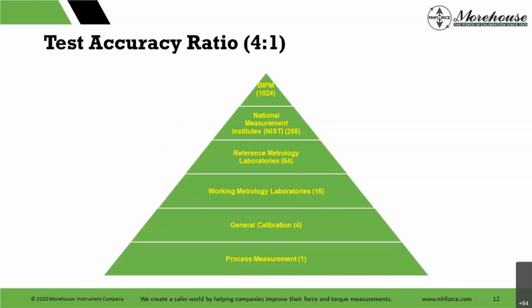Okay, thanks. So talking about accuracy, talking about uncertainties, there's this concept called T.U.R., where Jerry Hayes and someone else with the Navy, in the 1950s, basically came up with this concept of a 4-to-1, a 10-to-1 T.U.R. It was a stopgap solution until better computing power was available, right? In the 50s and 60s, they wanted general rules. And they came up with this concept of a test accuracy ratio, which basically said, hey, if I'm calibrating this standard, I want to make sure my reference standard is at least 4 times better than that standard. A lot of people still use this today, and it's problematic.